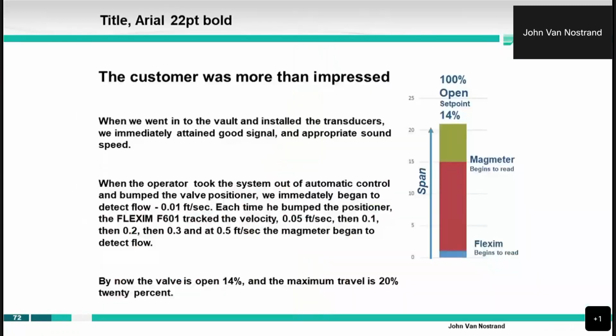So when you look at the span of the meter, the set point is at 14% of the valve. That Magmeter, that's only about 22 gallons per minute. That Magmeter would only begin to read at 15 gallons a minute. Look at where the FLEXIM meter began reading: less than 5 gallons a minute. So it's amazing that the customer was able to get that much more range out of his system and have that much tighter control of that valve position using the FLEXIM meter over a leading brand Magmeter. So that's a very powerful illustration of the capability of FLEXIM.